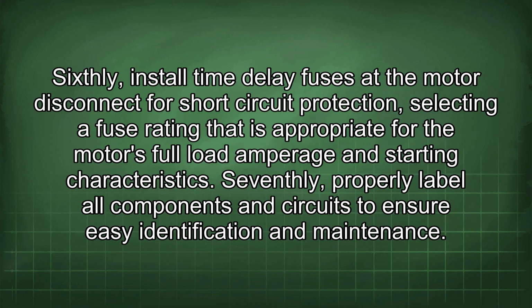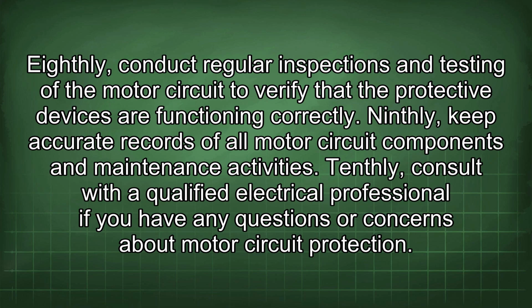Sixthly, install time delay fuses at the motor disconnect for short circuit protection, selecting a fuse rating that is appropriate for the motor's full load amperage and starting characteristics. Seventhly, properly label all components and circuits to ensure easy identification and maintenance. Eighthly, conduct regular inspections and testing of the motor circuit to verify that the protective devices are functioning correctly. Ninthly, keep accurate records of all motor circuit components and maintenance activities. Tenthly, consult with a qualified electrical professional if you have any questions or concerns about motor circuit protection.